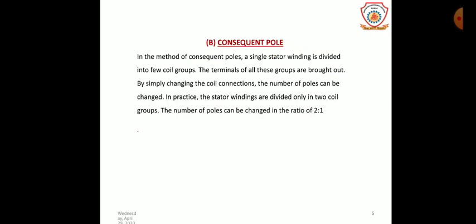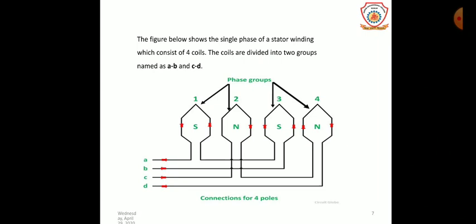In the consequent poles method, connections of stator windings are changed with the help of simple switching, due to which the number of stator poles gets changed in the ratio of 2:1, and hence either of two synchronous speeds can be selected. The figure below shows the single phase of a stator winding consisting of four coils divided into two groups, named as first group A-B and second group C-D.